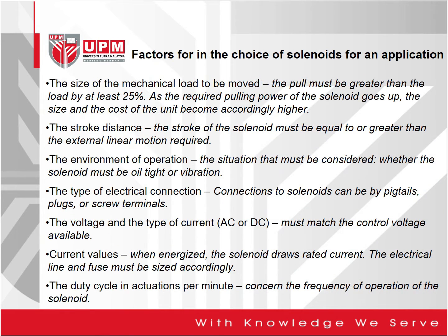So these are the factors in the choice of a solenoid for an application. The first one is the size of the mechanical load to be moved, the stroke distance, the environment of operation, the type of electrical connection, the voltage and the type of current, whether AC or DC, current values, and the duty cycle in actuations per minute.